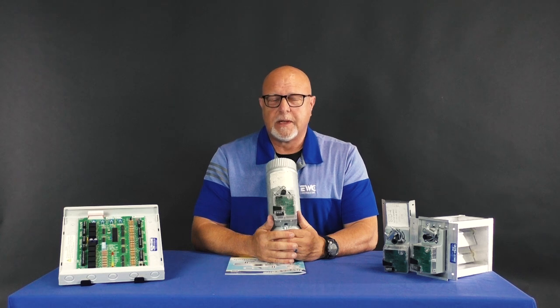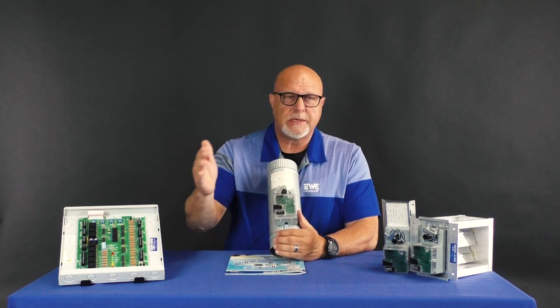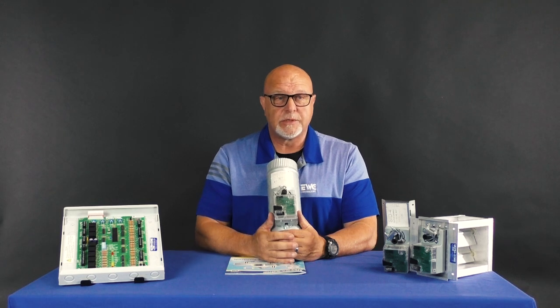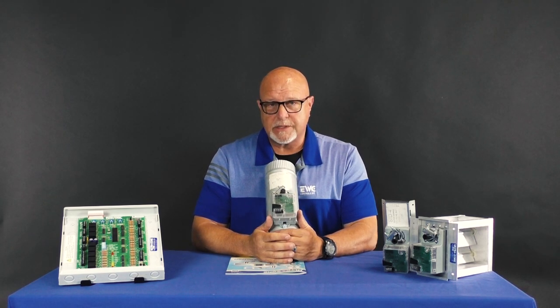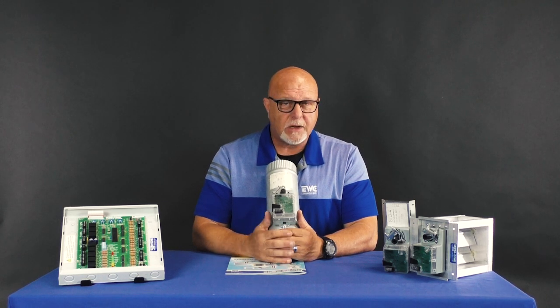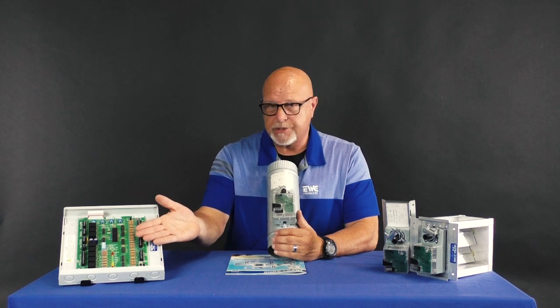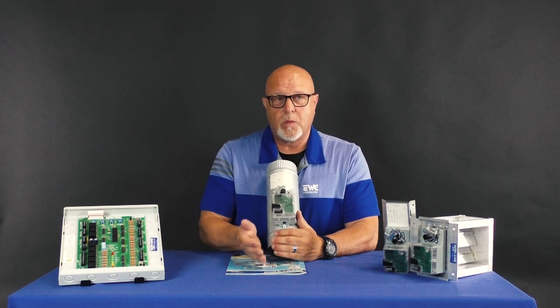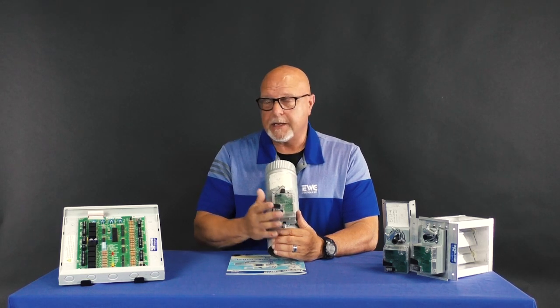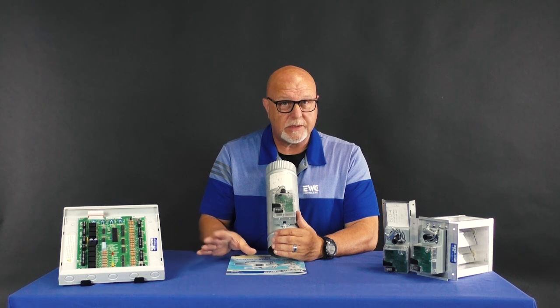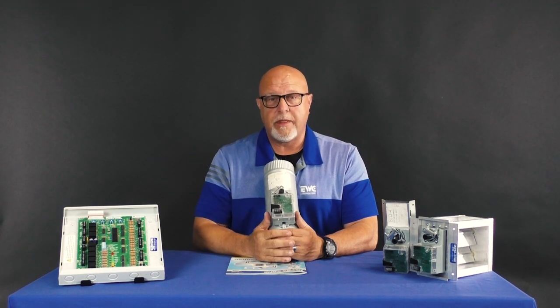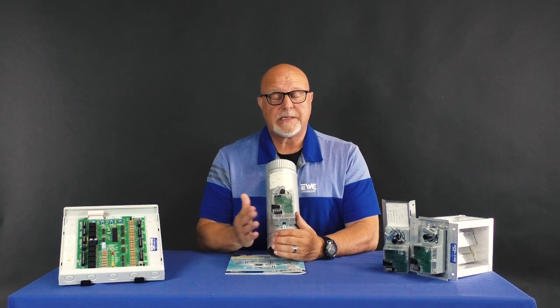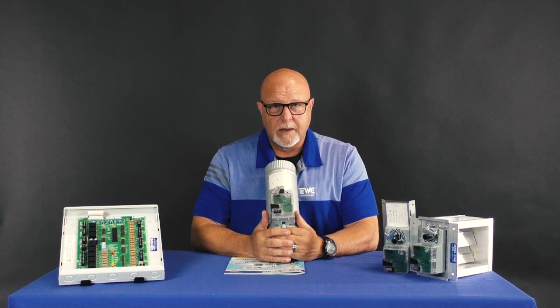Now when you're checking out a system, a lot of times the contractor will go damper to damper to make sure to look and see if that damper is open. This makes it very quick when you are checking out a system. These lights, being true position indicator lights, when you stick your head in an attic, you can see the call come to the board. You know that zone 1 is calling, and all the lights will be green. And if zone 2 is not calling, meaning the damper is actually closed, then all of those lights for that zone will be red. It makes it very quick and easy to commission your system, to make sure that the correct dampers are opening and the dampers that are supposed to be closed are closed.